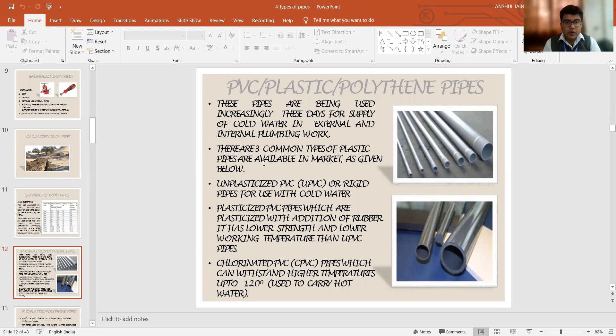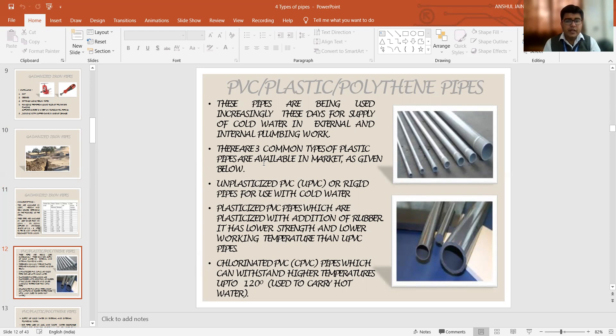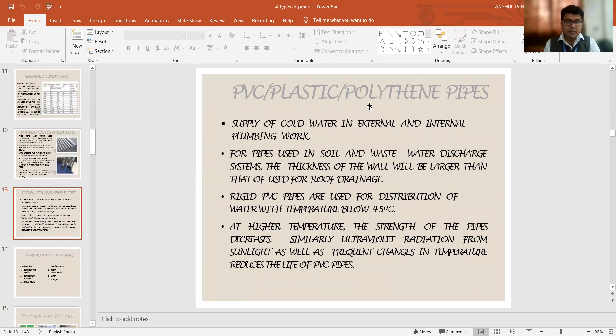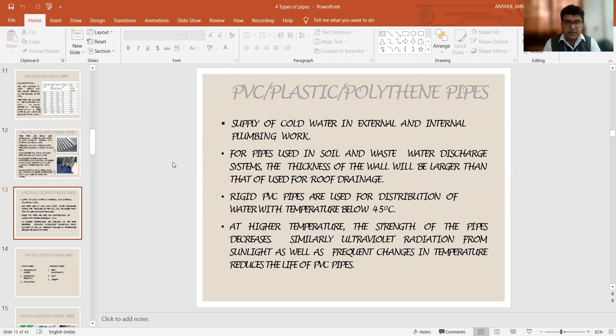The third variety is called chlorinated PVC pipes which can actually be at the temperature range up to 100 plus degree Celsius. So if you need to supply hot water directly from one end to the other end, we can go for this CPVC pipes, that is chlorinated PVC pipes. The supply of cold and hot water is possible with the help of these plastic pipes. The thickness can be varied as per the requirements.